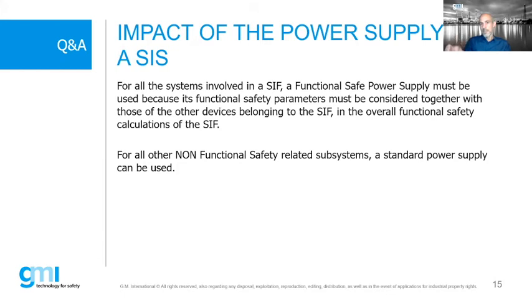So the power supply is very, very important. If we are not applying the power supplies for a safety application, a standard power supply can be used. In this case, the only difference from non-safety applications is that the safe power supply is not much more reliable, but we say that the reliability is proven. Why is it not proven on the standard power supply? As Massimo said before, components inside the safe power supplies are specific components with specific ranges and specific values. For standard power supplies, that is not proven. Maybe they are good, but the values are not proven.